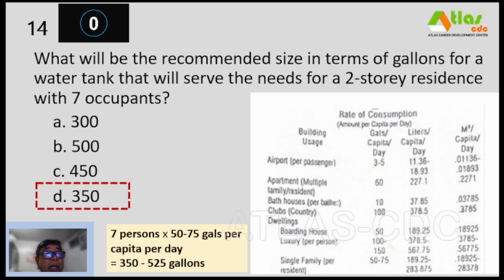So according to this table, for single family per resident is 50 to 75 gallons per capita per day. So if you have 7 persons times 50 will be around 350 gallons. Kung 75 gallons will be at 525 gallons. So the capacity of the tank should be from 350 to 525 gallons.